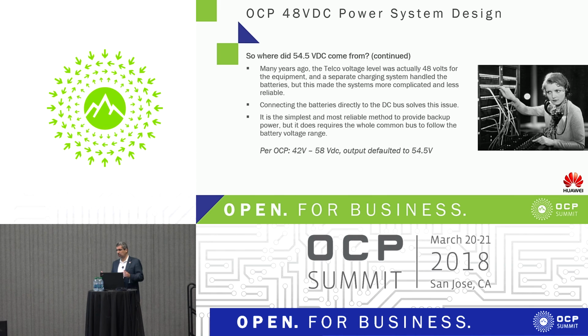The safest way to do that is to have the equipment and batteries on the same piece of copper, with nothing between them, maybe a breaker, but certainly no active components. So it's easier to float all the equipment at the same voltage, but that means the equipment has to live in a varied voltage environment versus a tightly regulated 48 volt environment. It has to float along with the batteries, but that makes it a lot more reliable.